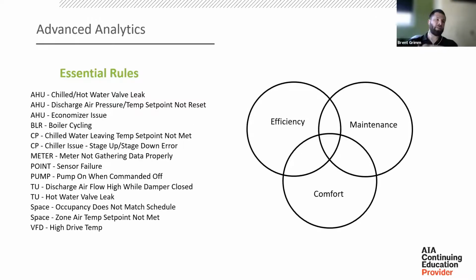I mentioned briefly in the last slide some rules, and rules are kind of the meat of advanced analytics. They're one of the key aspects of the analytics software that make it so powerful. Like I mentioned earlier, rules are condition-based algorithms that are used to evaluate the performance of a particular piece of equipment. So one easy example of a rule is a leaking chill water valve rule for an air handler.